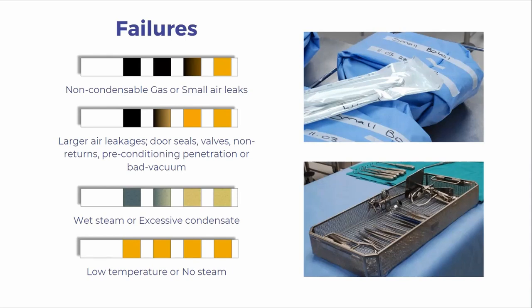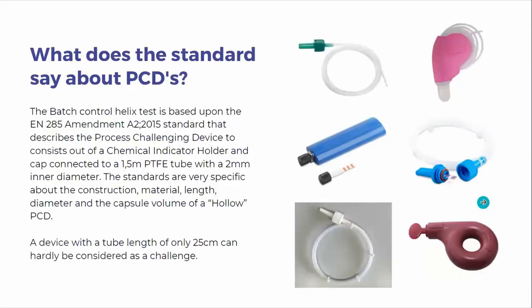Why the Helix is becoming more and more popular is not a surprise, given the many failures it can detect. EN285:2015 is now the current standard and the latest version, and supersedes the old EN285:2006 + A2:2009. So the latest one is the 2015 version. But what does the standard say about PCDs? The batch control Helix is based upon the EN285 standard that describes the process challenge device to consist of a chemical indicator holder and a cap connected to a 1.5 meter PTFE tube with a 2 millimeter diameter. The 2 millimeter diameter is the inner diameter. It's not the outer or the cap size. It's the pipe of the device that's the 2 millimeter.